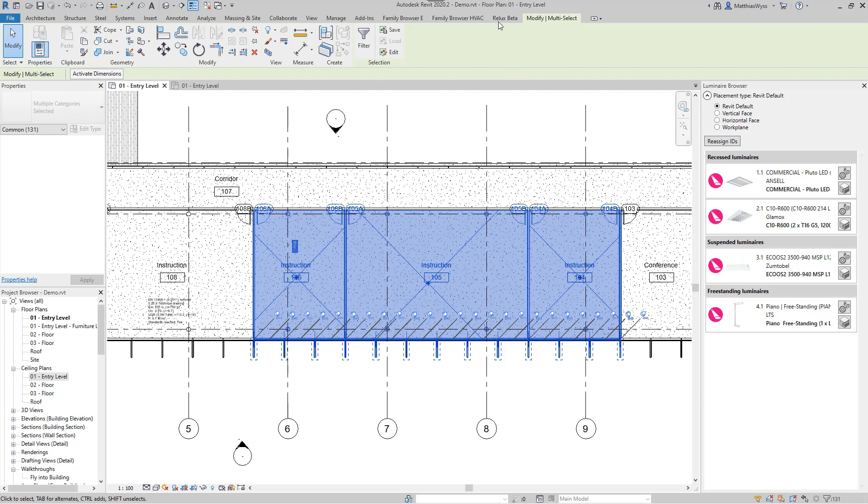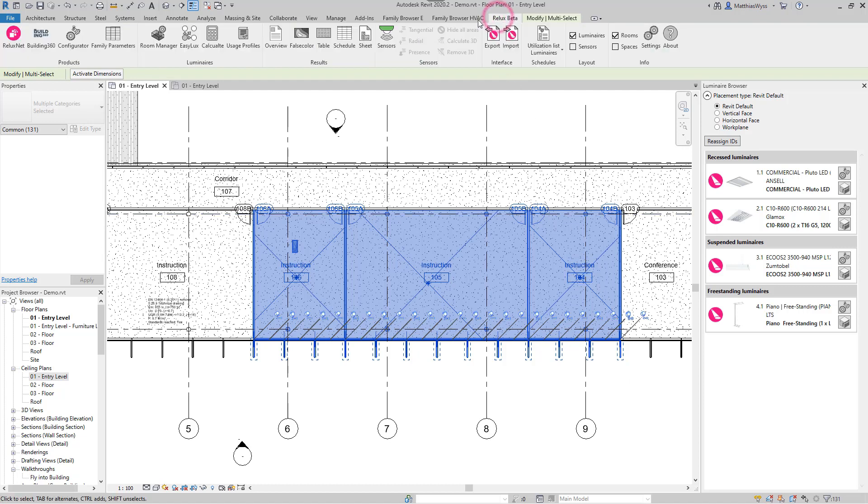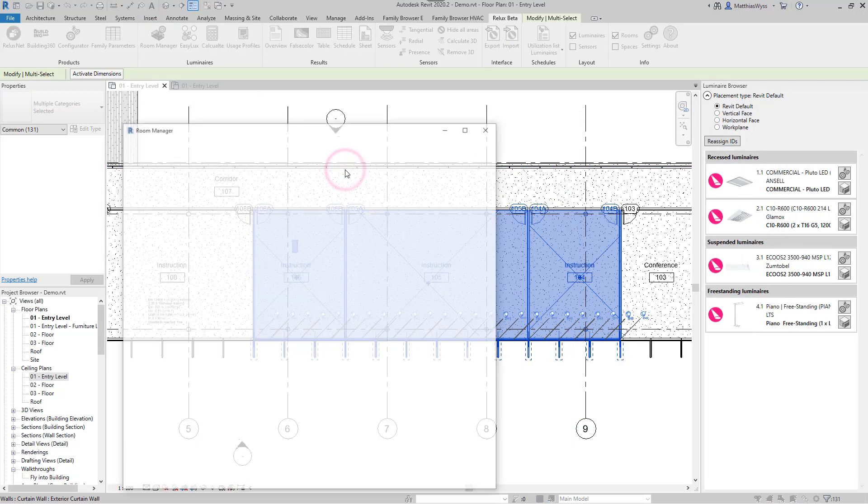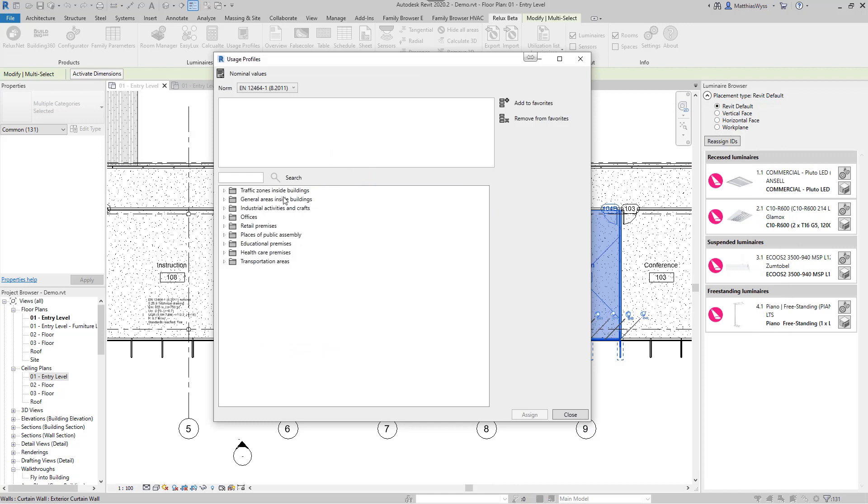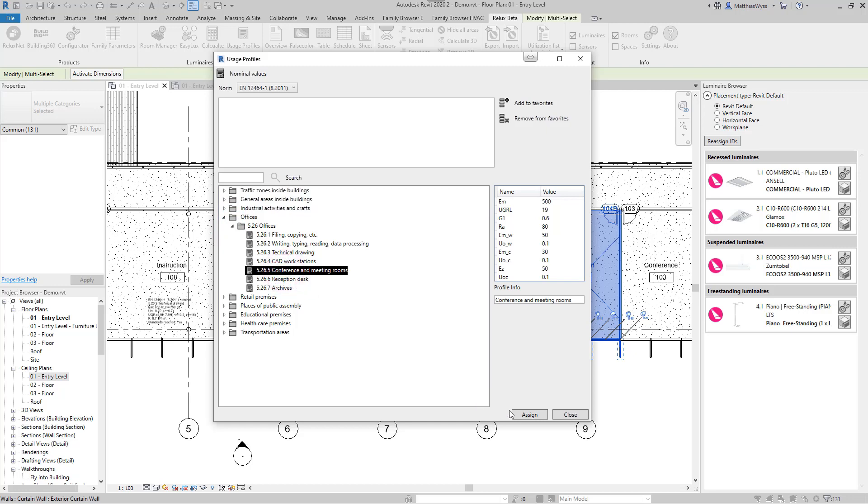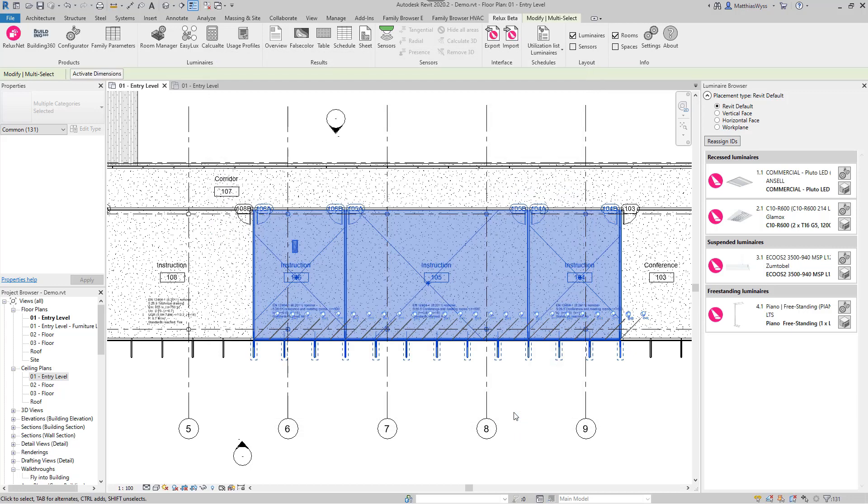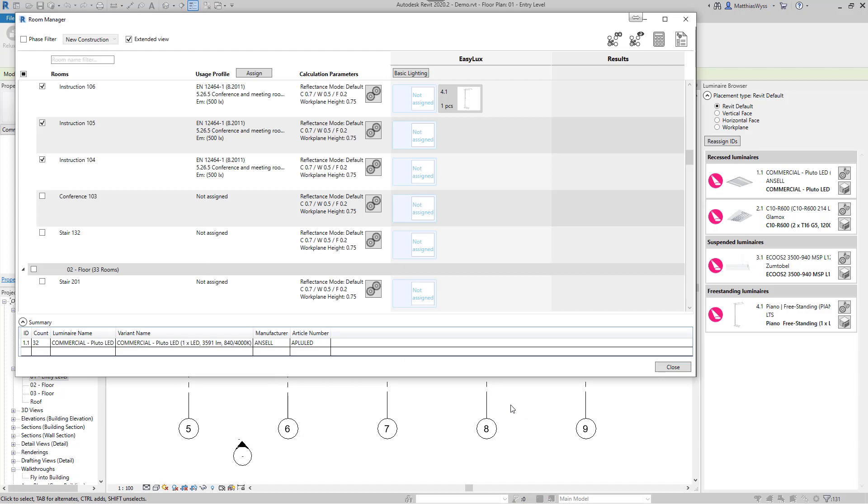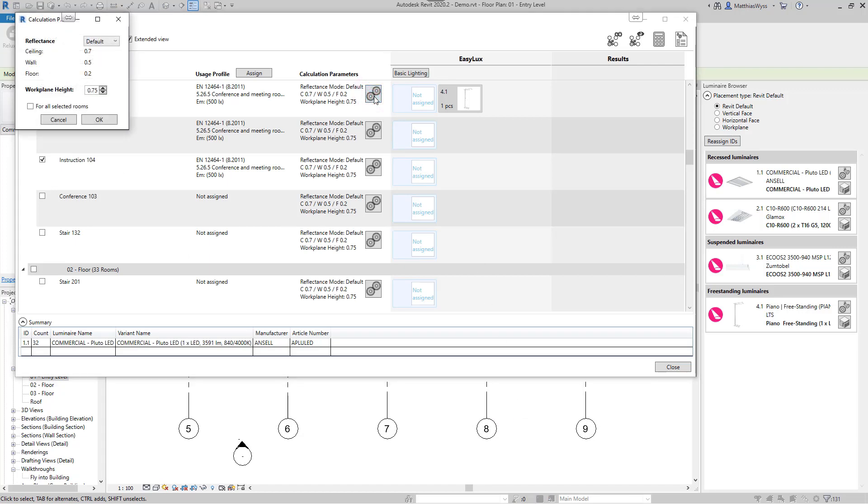In the Room Manager, we can perform the calculation and placement for several rooms or for the whole building. We assign a usage profile to the selected rooms. In the calculation parameters, we can set the reflection degree and the work plane height. The latter is set directly to the correct height when a usage profile is assigned.